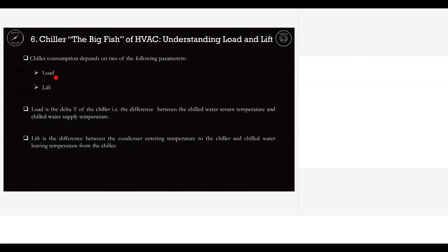This is the difference between the supply and return chilled water temperature. And the lift: there are many definitions of lift, but basically it is a delta between the operational temperatures of the evaporator and the condenser, or the operational pressures of the evaporator and the condenser. So that is the lift through which the compressor is compressing the refrigerant from the evaporator to the condenser. So both these things control the consumption of energy. That is what is written here.